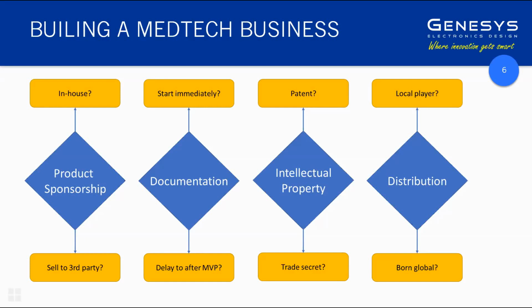investment. However, one of the things with active medical devices, particularly on the software side of things, is that any work you do without documentation is essentially worthless. It has to be actually redone with documentation in parallel with the development work, starting with the identification of user requirements. So that is an initial burden right up front if you make the decision to start documentation early, but it really does save you a lot of effort down the track.